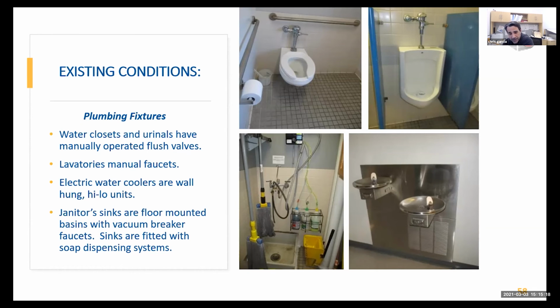One of the typical issues we find is cross connections when it comes to these soap dispensers at the mop receptors, so we can look at that further. I didn't see any backflow preventers on those systems, so those can tend to sometimes allow hot water to migrate throughout the systems if you're still having those problems.